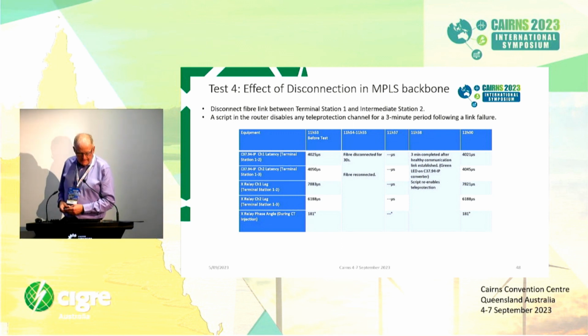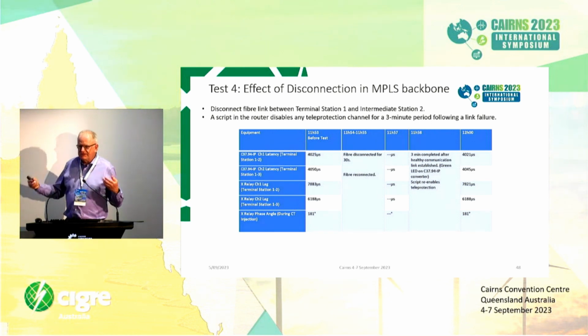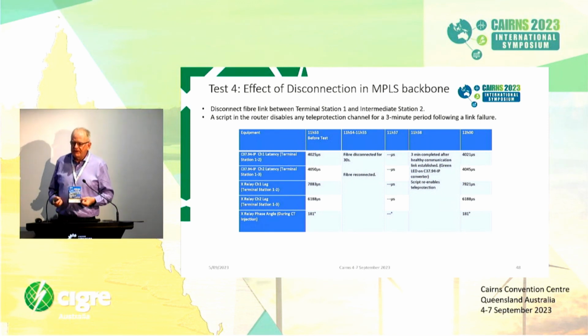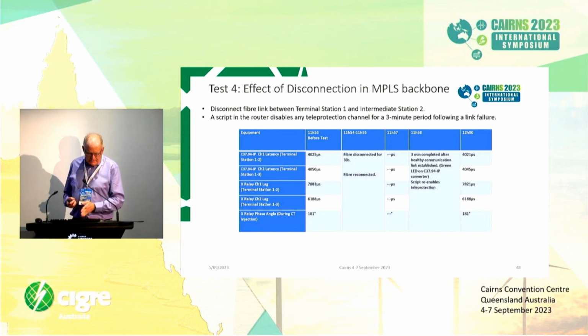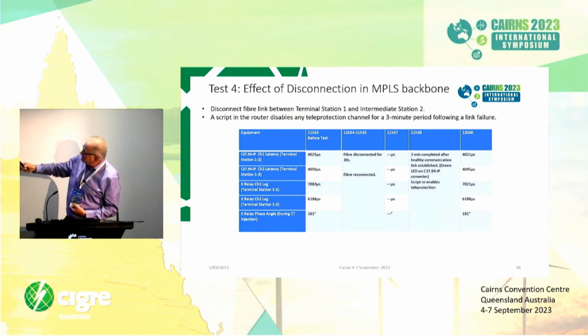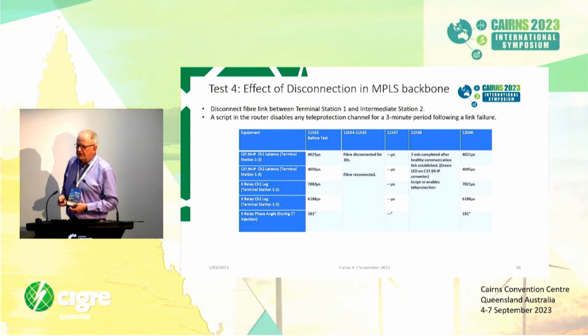In fact, when the backbone goes down, we figure that the relays are still receiving the simulated C37.94 signals from each end with the time, and that's how they're getting their clocking source for operation. So observation here, we think this is correct, that we're not seeing any difference in latency calculations or phase angle calculations between the pre-test and after the test. All those figures are identical, or very close. So we think that the relays aren't really recalculating their round trip times during this particular test.